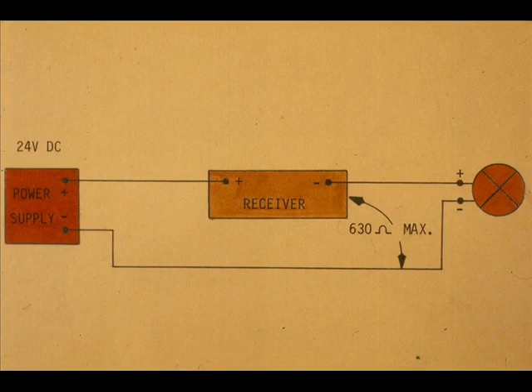Either a millivolt meter shown here or a digital volt meter may be used. With 24 volts DC supply, the loop resistance, including the signal wires, should not exceed 630 ohms.